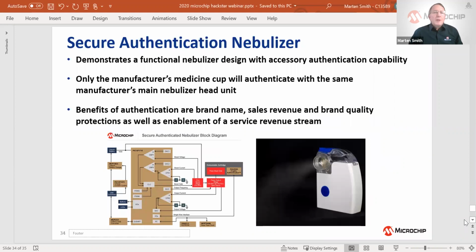One more thing: we took that nebulizer design earlier and showed how to do a secure version. One thing that's important in security, another authentication scheme besides web authentication, is how do I authenticate an attachment or an accessory or a peripheral. If I've made a medical device that has something disposable that always gets replaced with new ones, there's always that threat of somebody counterfeiting that, and people buying the counterfeit version and using it with my medical device. Things like probes, or in this case, a medicine cup for a nebulizer, which happens to be disposable.